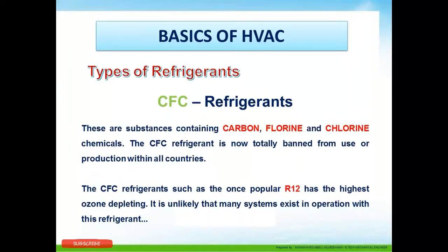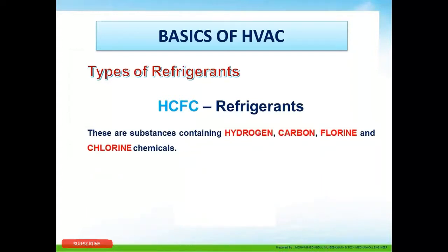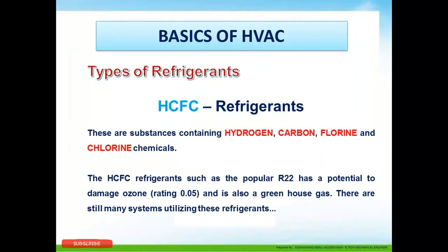CFC refrigerants are no longer used and are totally banned in all countries. HCFC refrigerants are substances containing hydrogen, carbon, fluorine, and chlorine. The HCFC refrigerant R22 has potential to damage the ozone layer and is also a greenhouse gas. R22 is already banned and is no longer being produced, though it is still found in existing systems in many countries and will need to be eliminated.